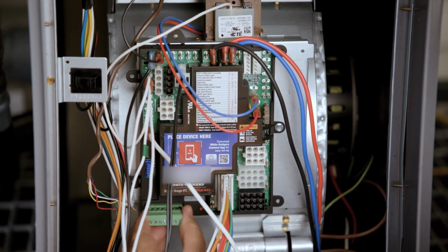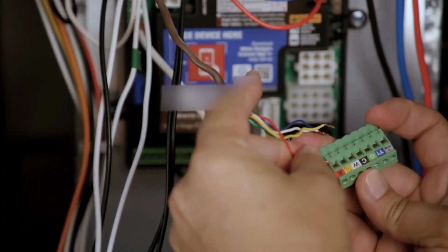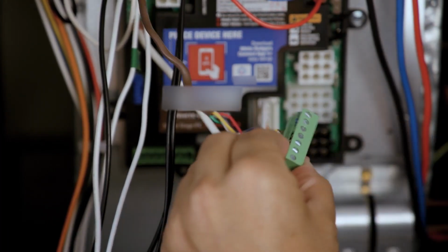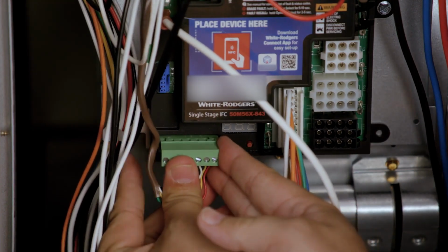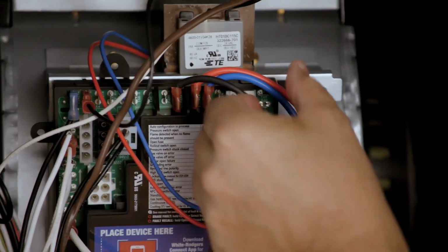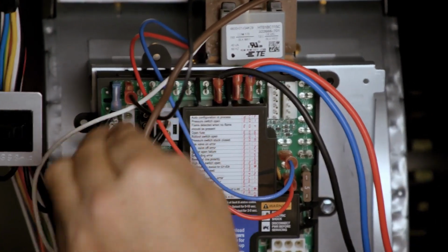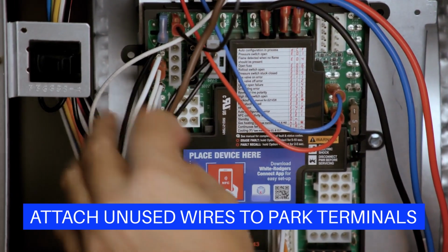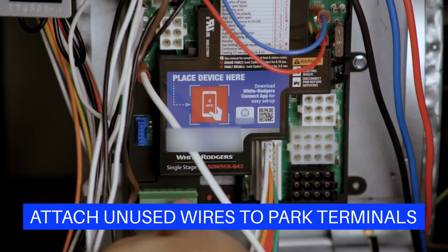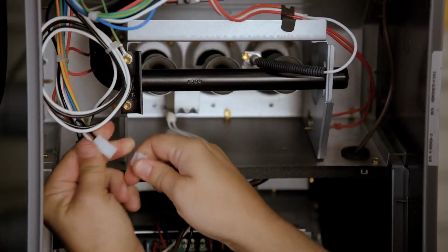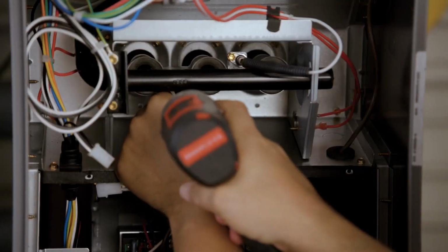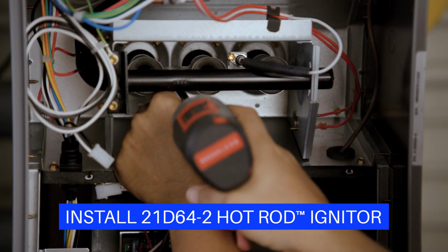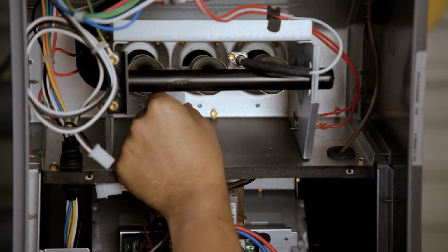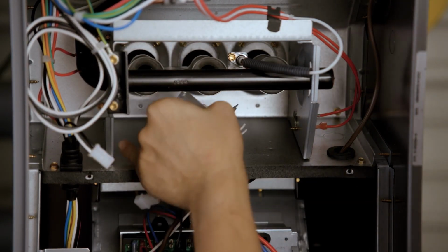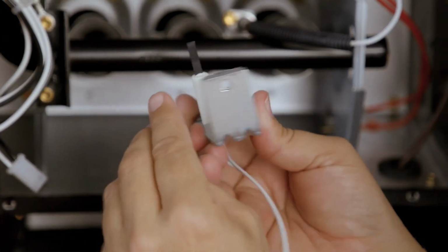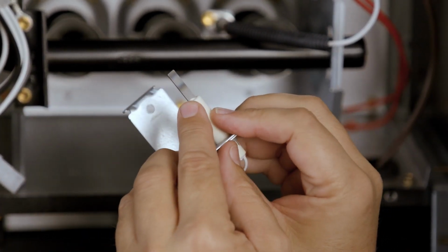Remove the thermostat bus block from the control and install the thermostat wires according to the terminals they were removed from. Then, plug the block back into the control. Ensure all wires and connectors are secured to the control board and any unused blower speed wires are attached to the Park terminals. If the control being replaced operated an 80-volt igniter, the existing igniter must be replaced with the included hot rod igniter. For all other applications, inspect the existing 120-volt igniter to determine if it must be replaced.